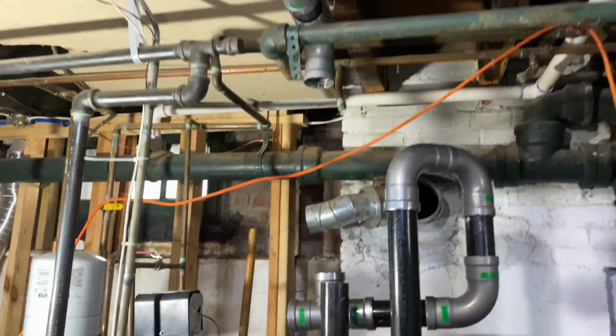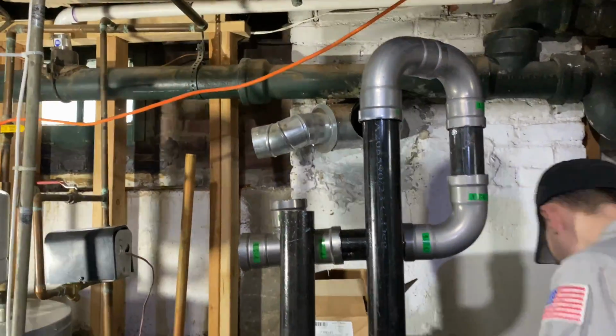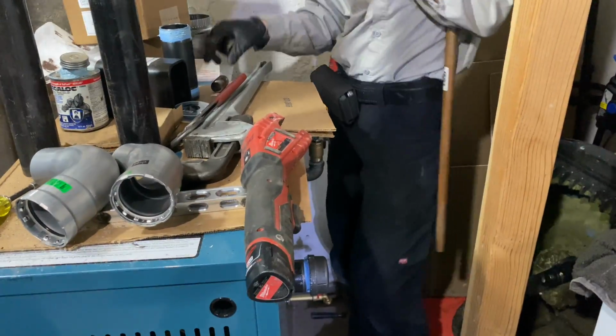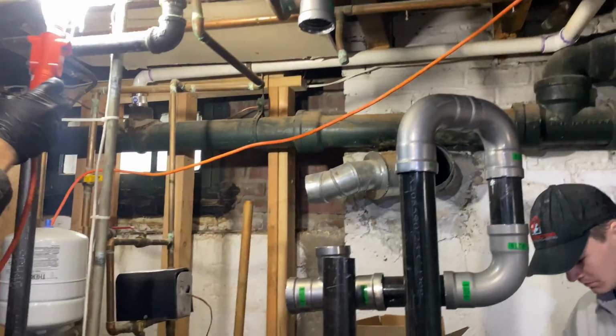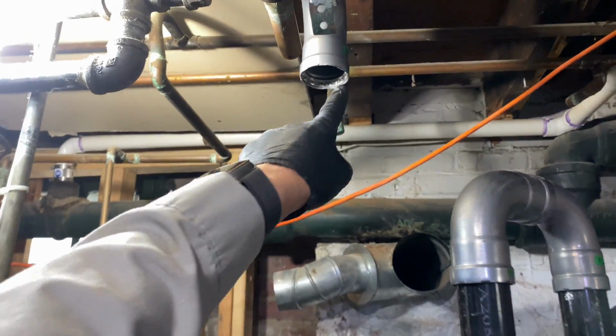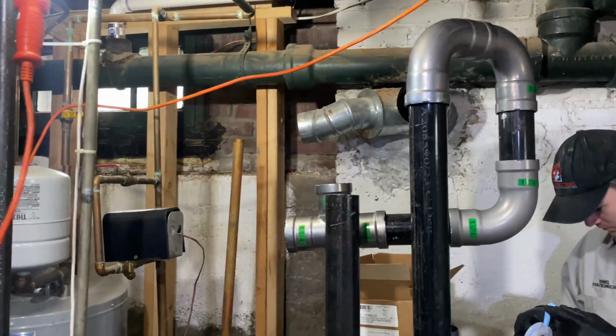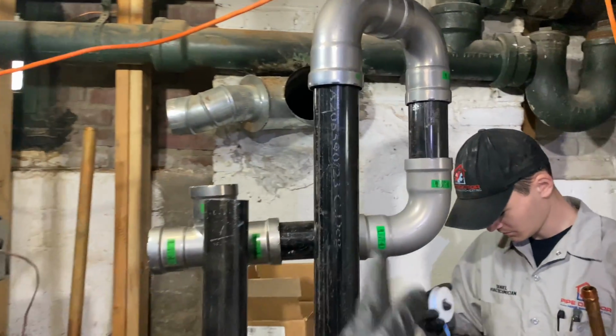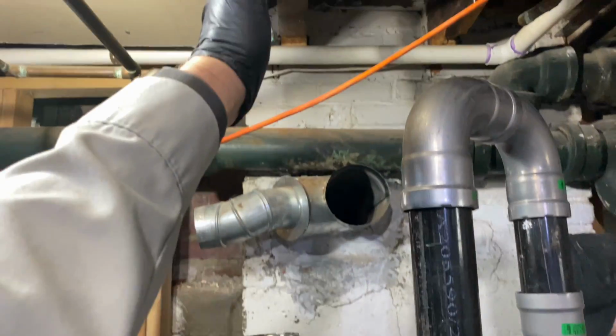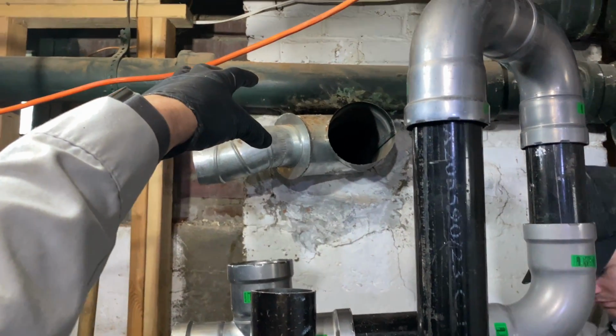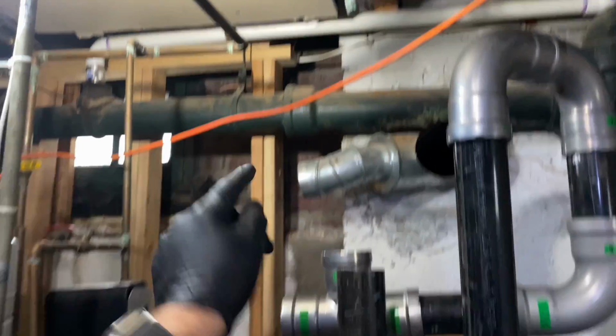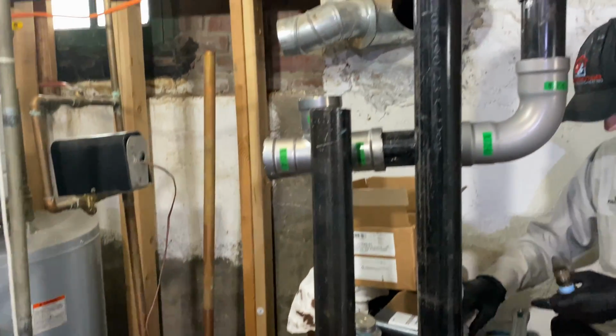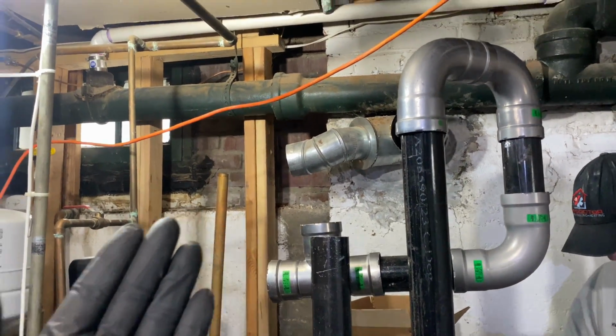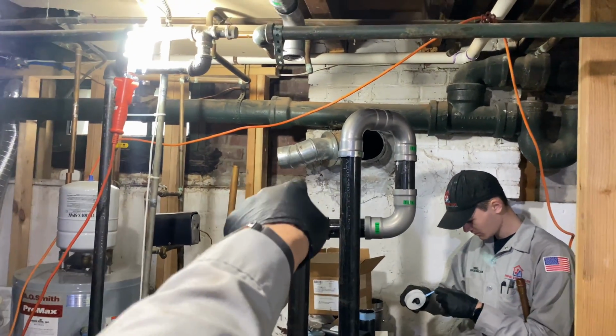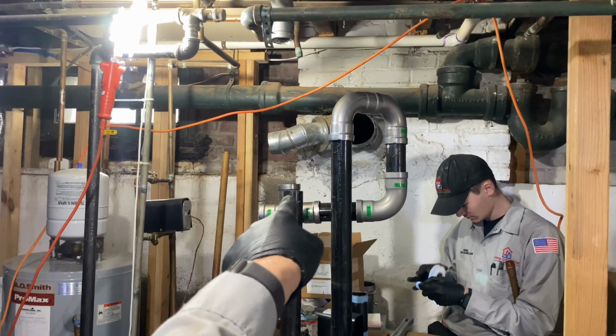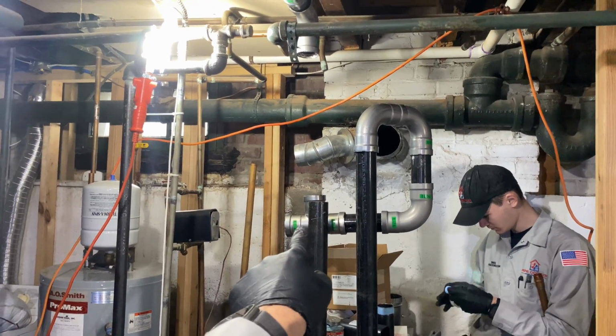All right, so we are working on the steam header piping while Daniel's working on the relief valve discharge. I need to connect this to there, and I also need to go there. I was thinking, if the steam is coming up here and going around, it's coming here first anyway, so why don't I add a T here and then pick up the two mains? This will continue on to my equalizer. So that's what I'm thinking, why don't I do that? I have a single steam main leaving that's going to pick up these two.